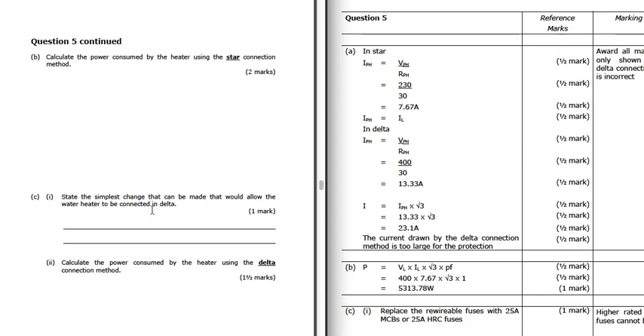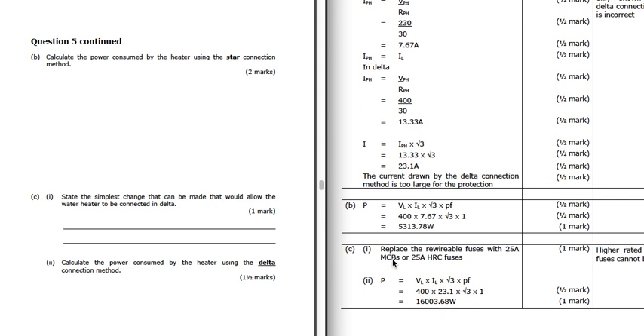State the simplest change that can be made that would allow the water heater to be connected in delta. So we would need a bigger rating of protective device, and we'd also change that rewirable to an MCB or an HRC. We wouldn't put a higher rated rewirable. We wouldn't replace it with a rewirable. We'd go with the MCB or HRC.